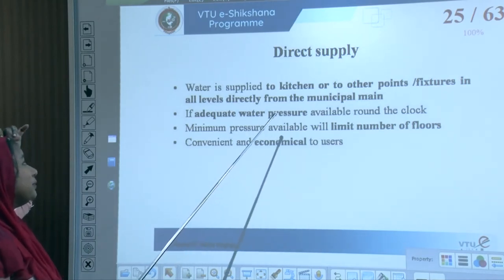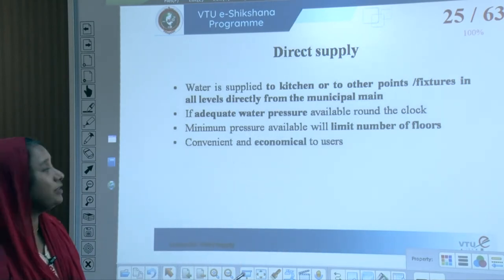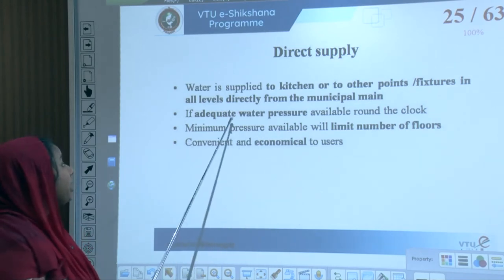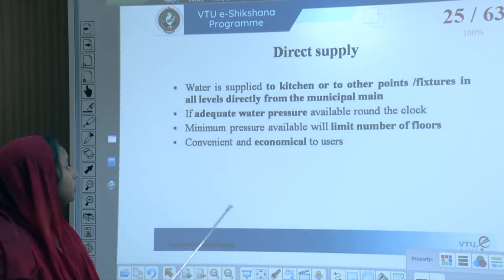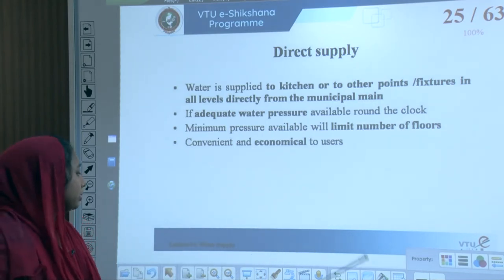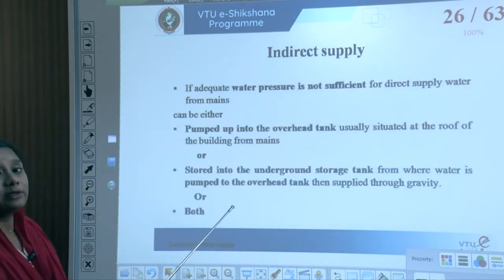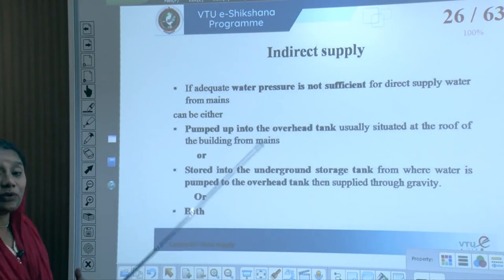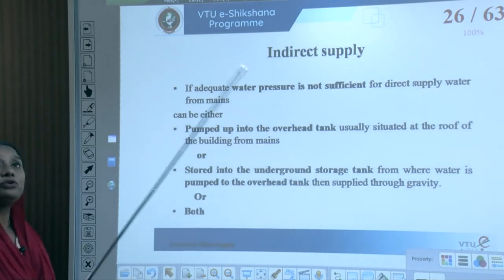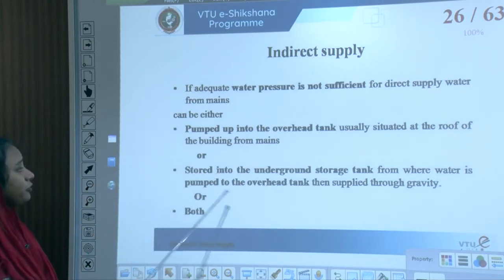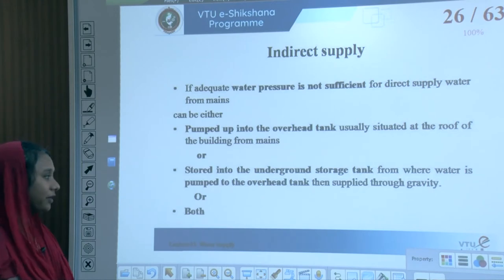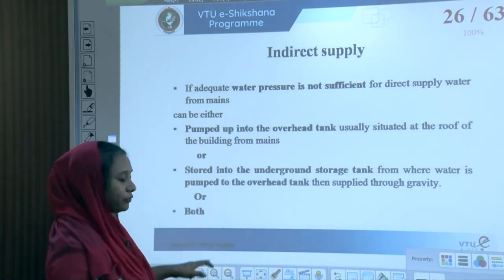Direct supply is water supplied directly to the kitchen or other fixtures at all levels from the municipal main. This requires adequate water pressure available around the clock and is convenient and economical. Indirect supply is used when adequate water pressure is not sufficient — water from the mains is either pumped into the overhead tank at the top of the building, or stored in an underground storage tank from where it is pumped to the overhead tank and supplied through gravity.